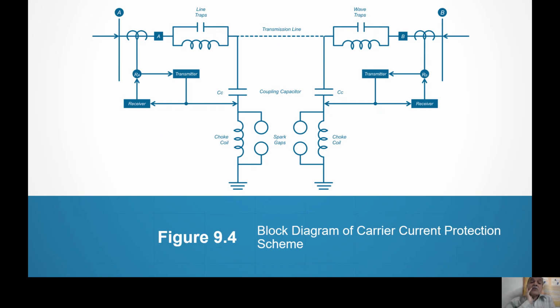Right. Over and above, you can see a choke coil is provided. When I say the power signal is not passing through CC, note that Xc is 1 upon 2 pi Fc, and F is 50 hertz, so it is very small, but that small current will pass through. That small current can also go to the carrier equipment and can damage it. So that it does not damage, the CC and choke coil make a series resonant circuit. And whatever small power signal, if at all it comes, is grounded. That is the function of the choke coil. Spark gaps are kept to protect the choke coil against lightning strokes. So this is the figure of the carrier equipment.